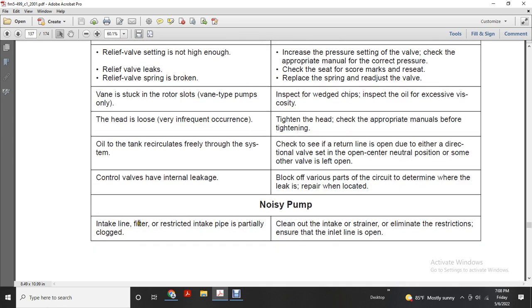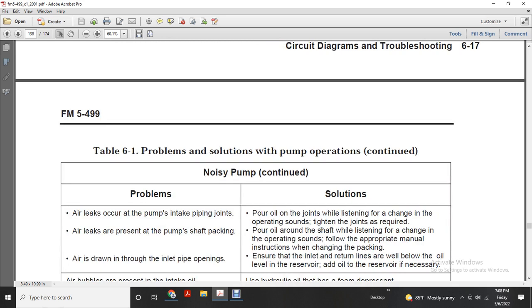Noisy pump, intake line, filter: restricted intake pipe is partially clogged. Clean the intake strainer, eliminate restrictions, and ensure the inlet pipe is open. Noisy pump continued: air leak at the pump intake piping joints, or air leaks in the pump shaft packing, or air is drawn through inlet pipe openings. Pour oil on the joints, listening for a change in the operating sound, and tighten the joints as required. Pour oil around the shaft, listening for a change in the operating sound, and change the packing following the appropriate manual instructions.